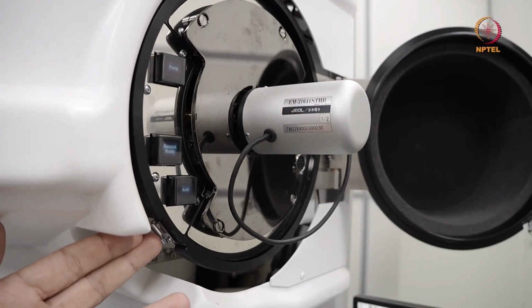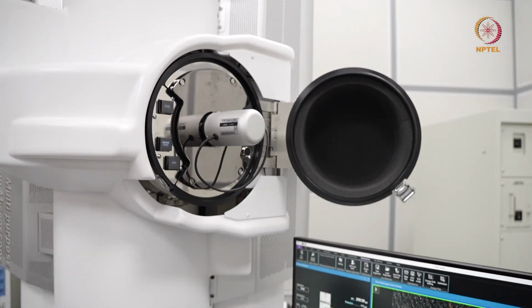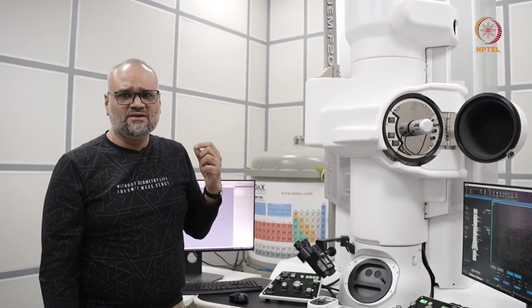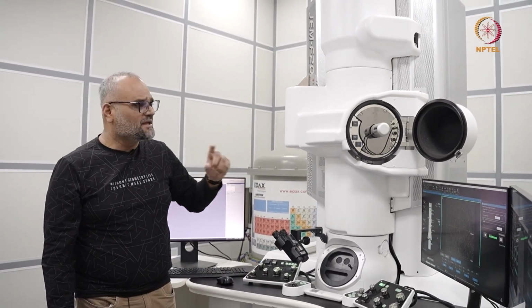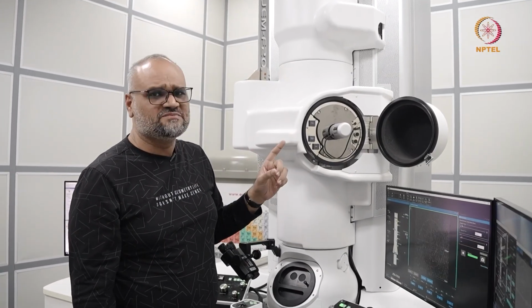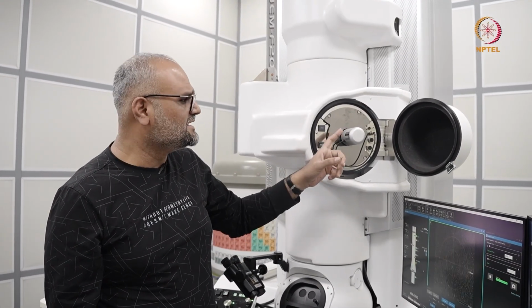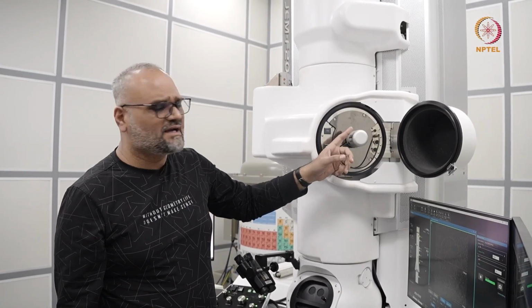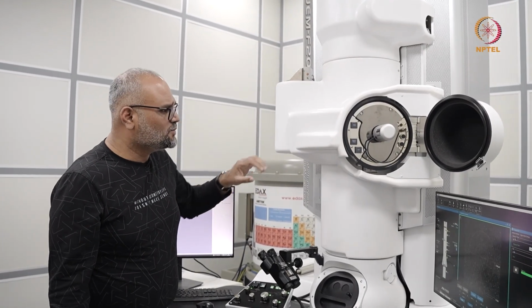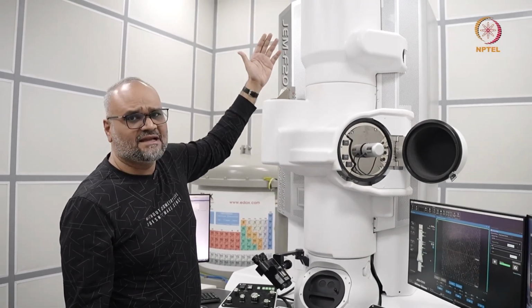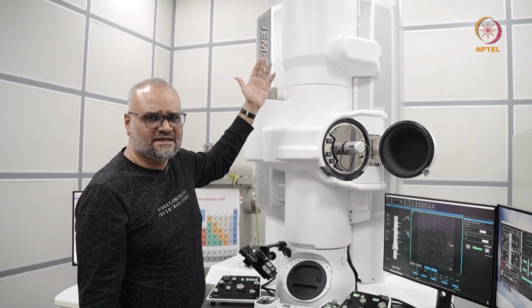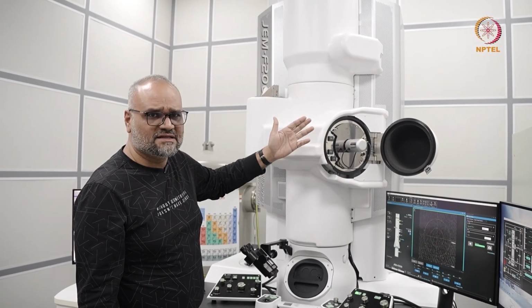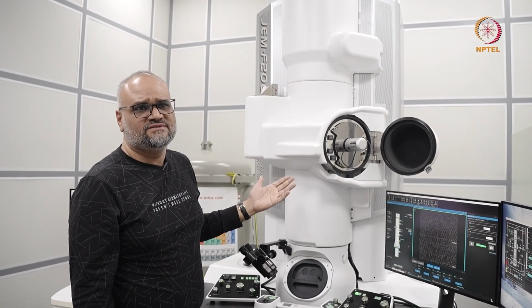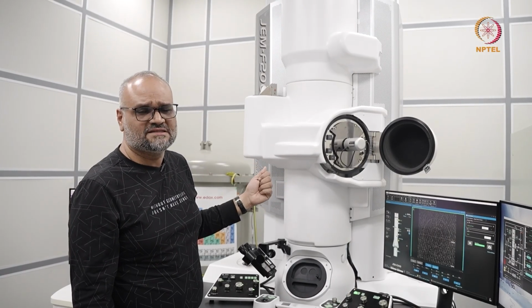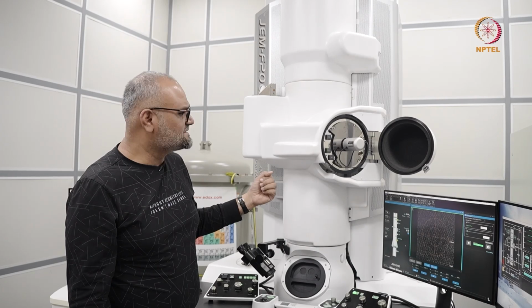So here you can automatically load the holder into the microscope. So once you carefully load the specimen into the holder, it goes in automatically. Bear in mind, not all holders are compatible with the spec porter. You should check for the compatibility. Typically an indication is this gray back that you have here. So with that, once the holder is inserted, I will start by aligning in the same sequence, starting with the condenser aperture and aligning the eucentric height, and then depending on the modes of imaging, I will correct for the astigmatism of the objective lens, or if I am doing STEM mode, I will first correct for the astigmatism of the condenser lens.